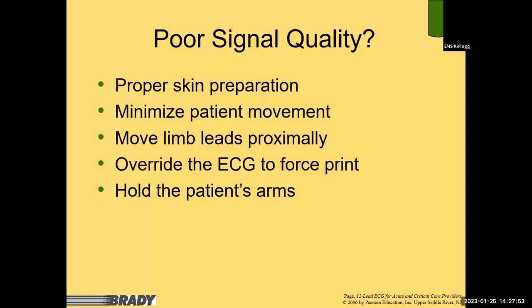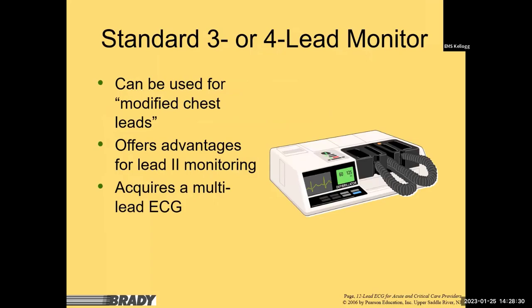Sometimes the 12-lead machine will pop up saying 'too much artifact' and won't generate a printout. If you override and force print, the computer algorithm reading will not be accurate. If a patient has Parkinson's, you can put a little gentle traction on their arms and the tremors will stop — that makes a big difference for getting a clean tracing.